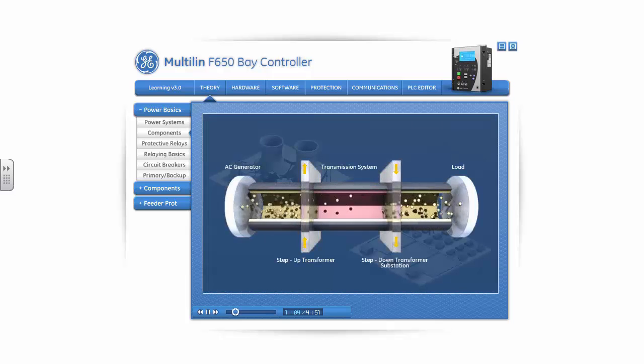Once generated, the voltage is fed to step-up transformers for transmission to reduce the I²R losses, and then at the substation it is stepped down for distribution. Given that the power loss during transmission is equal to the current squared flowing through the transmission line times the resistance of the transmission line, the step-up transformer increases the voltage level, thereby reducing the current, resulting in an overall reduction of power loss during transmission.